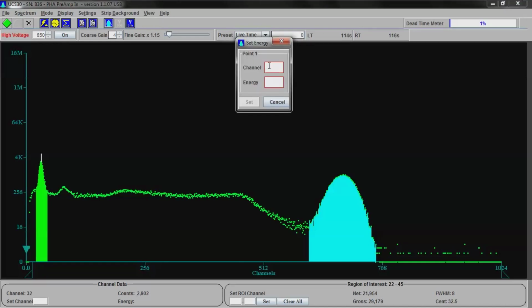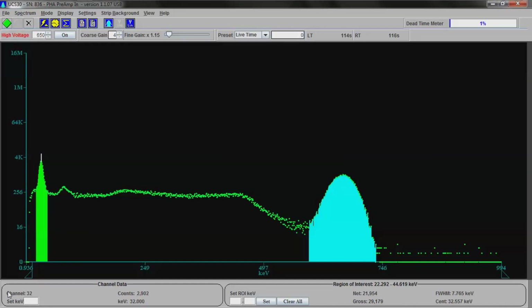And we're going to tell the machine that channel 32, that's right here, happens to be equal to 32 kiloelectron volts. I chose these settings for that reason. But then we're going to tell it that this channel over here, now what was that channel? 681? We're going to tell it that channel 681 is equal to 662 kiloelectron volts. And now all the bottom here changes to kiloelectron volts.